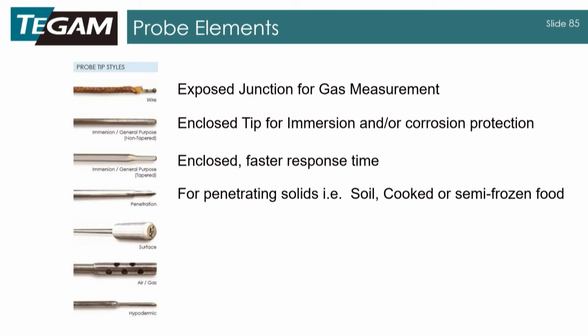And this next one is for penetrating solids. This is going to be something that's used a lot of times in the food industry, checking the temperature of the chicken or whatever through the process. This next one's a little interesting. This is a surface probe to measure flat surfaces. One thing you'll notice though are these little spring looking things at the bottom. Now what that is, that's actually your thermocouple junction. Technically you can call this an exposed probe, because when you take this surface probe and push it against your surface, these spring into the probe to make good contact with the thing that you're measuring, so you can get a good measurement of that flat surface. So while you do have the sheath and you do have the ceramic, when it's all said and done, you do have an exposed thermocouple at the end. You're not going to be measuring gas or anything like that with this one, but it's great for a flat surface measurement, especially with that spring tension in there.